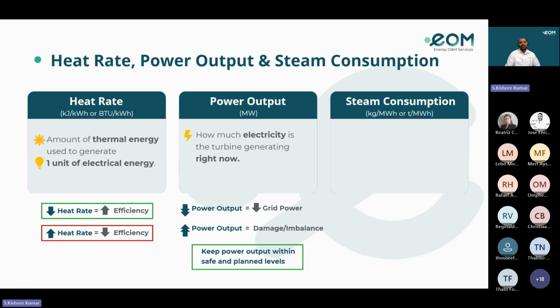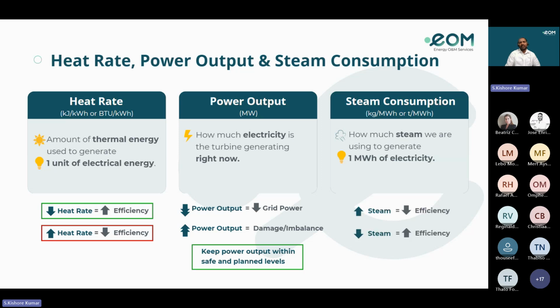Coming to the steam consumption, what is it? It is how much steam we are using to generate 1 megawatt of electricity. If you need more steam to make the same electricity, it means the system is less efficient. If you need less steam, your turbine is running better and more efficiently. So why does it matter? Steam is costly. It comes from burning fuel and boiling water, and a lot of losses occur in the process. So less steam per megawatt means better performance and lower operating costs.